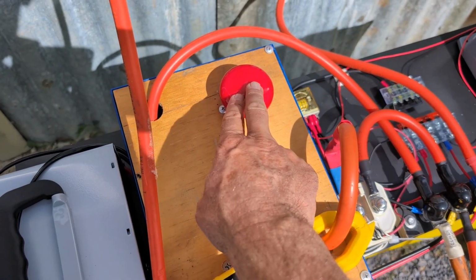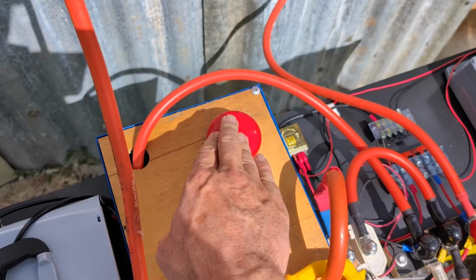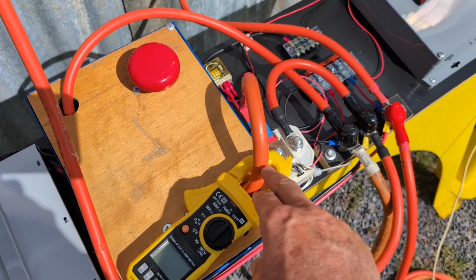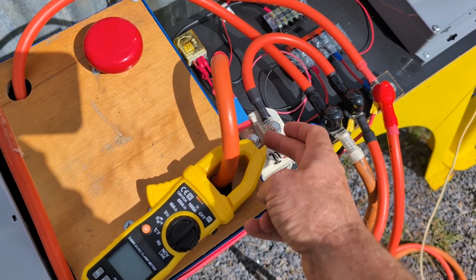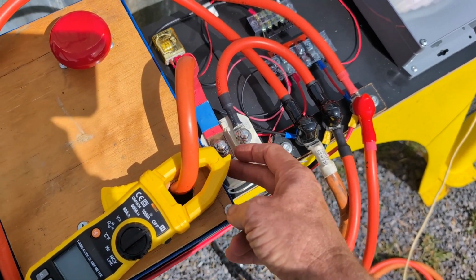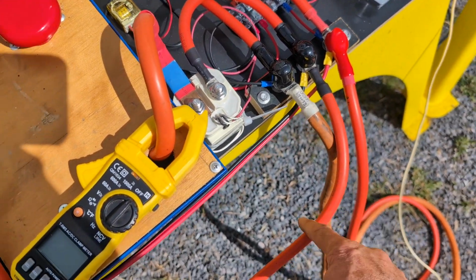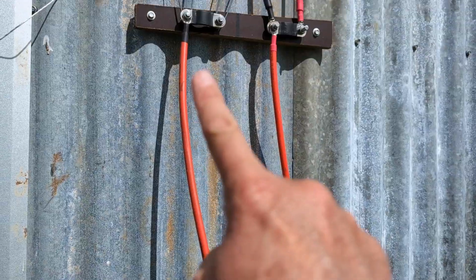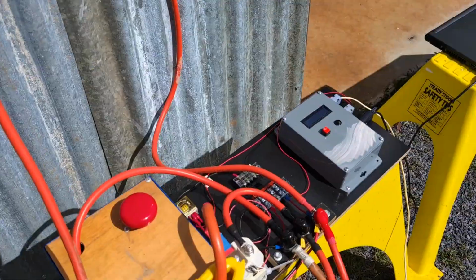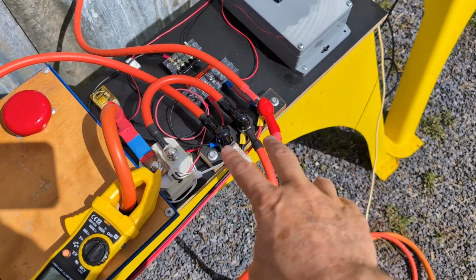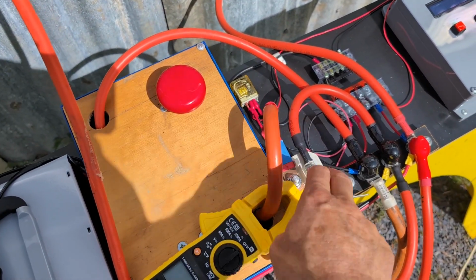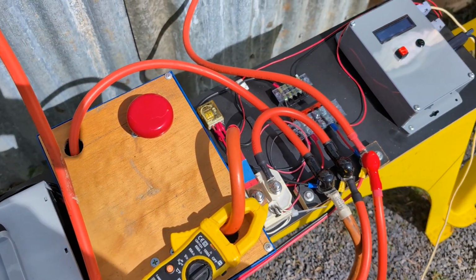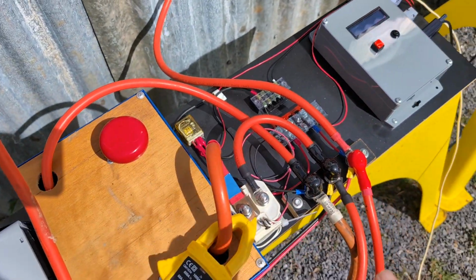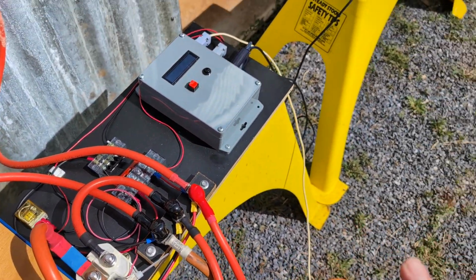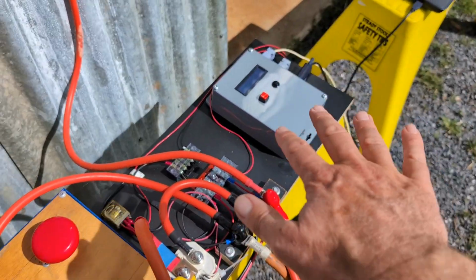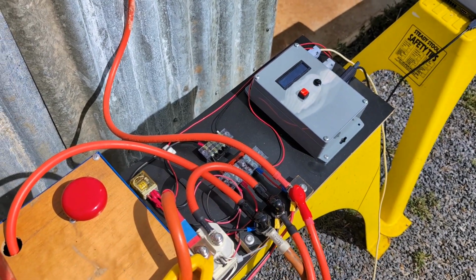First through an emergency stop, through an isolation switch, so I've got that isolated at the moment, through a fuse, and then into this contactor. This contactor is controlled by the BMS, and then through to this one is the wire. So we can connect the wires to the battery through these two switches here, the contactor and the manual switch here. At the moment I've got it disconnected, so I should be able to connect the battery back up now, and it will power the BMS and everything, but won't do anything else.